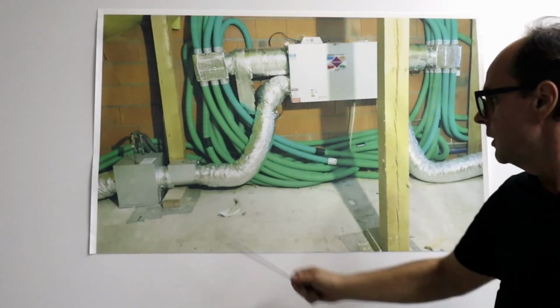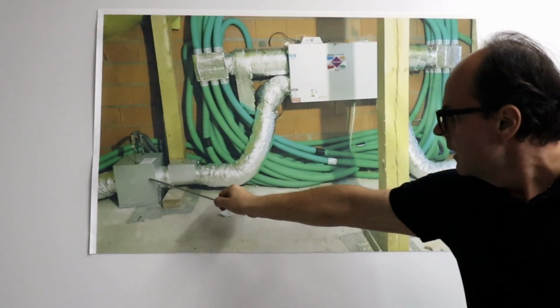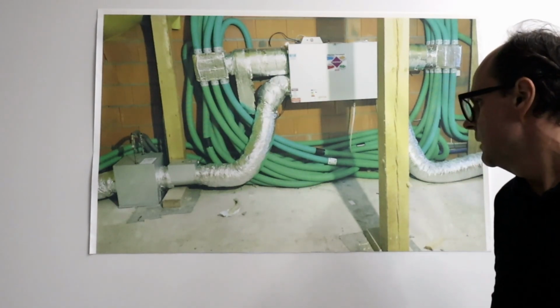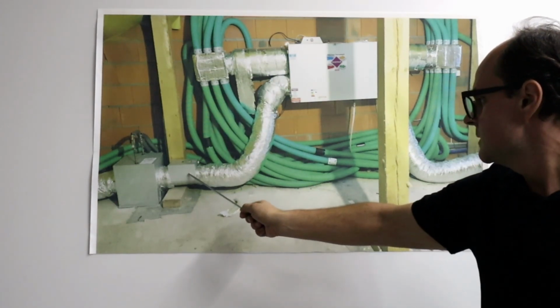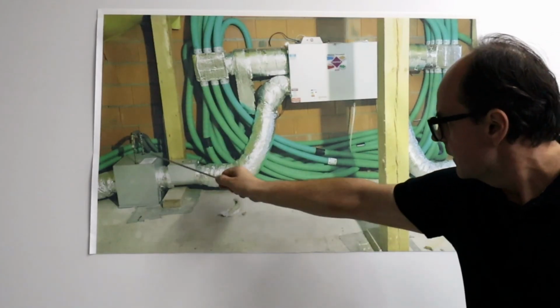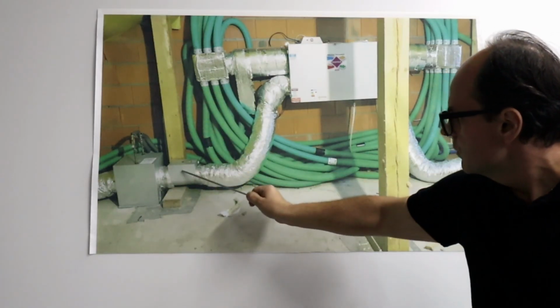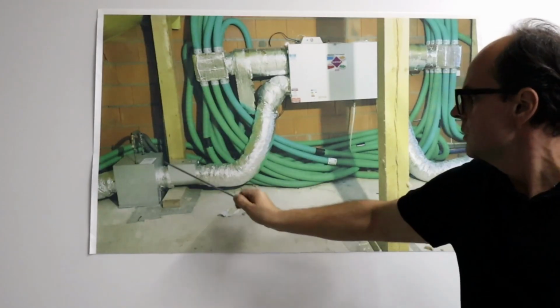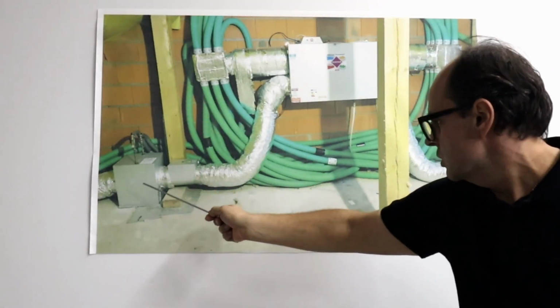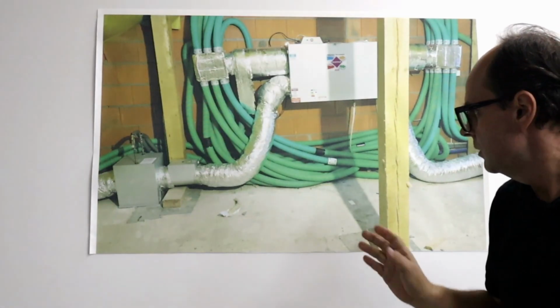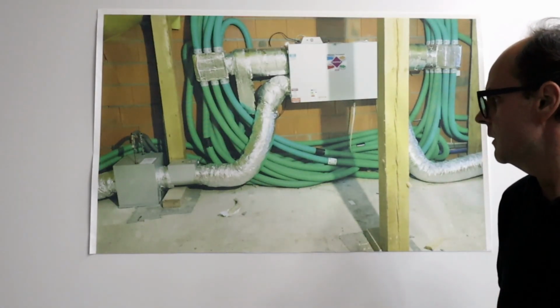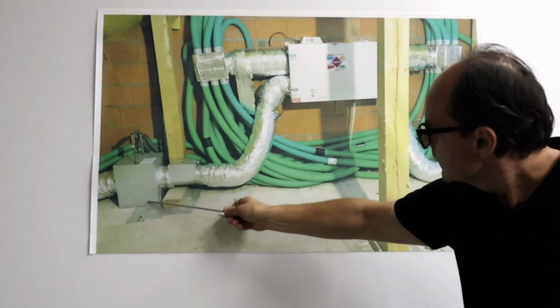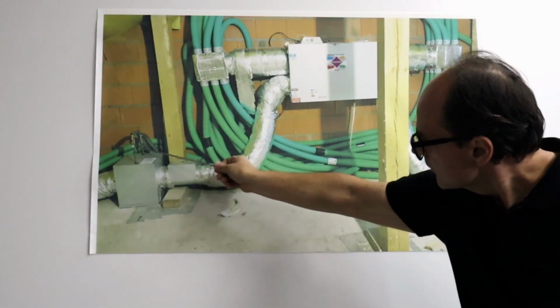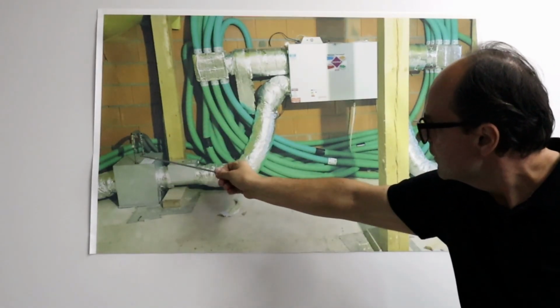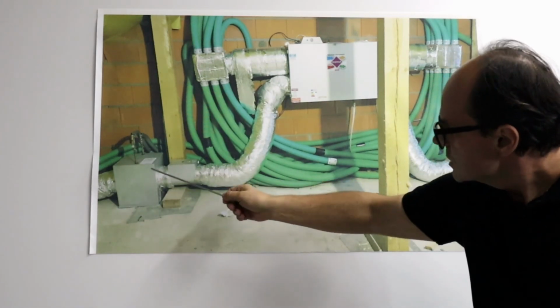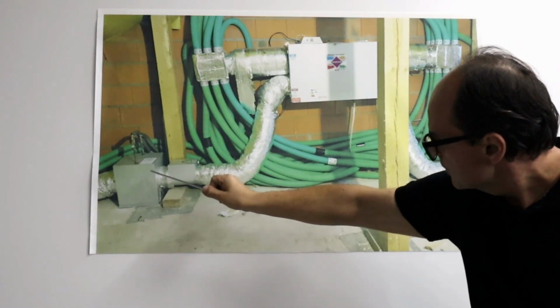If it was intended to be a water-based heater, in my opinion, this should always be placed behind an electric heater. If the water or glycol unit isn't enough, we add an electric one, but it should be positioned a little closer. Although it can be connected either here or there, you could say this is not an error, but originally this was supposed to be a glycol cooler heater connected directly to a heat pump unit. These gentlemen, in an effort to save some money, decided to use a standard heater.